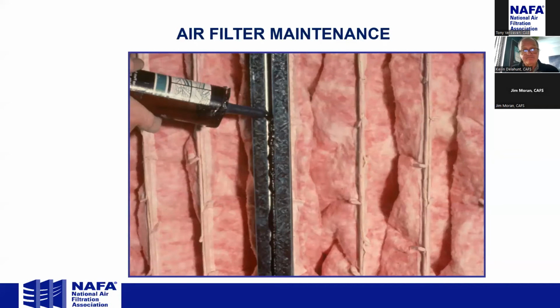Okay. Bag filters are a pretty common product in a lot of commercial buildings. In most cases, we like the air to hit it perpendicular, meaning that the air is actually helping in the seal by driving the filter into a gasket and a holding frame, as you saw in the picture back there. But in some cases, they're supplied as a side access in a U-channel tracking, and there could be 2 to 20 or 30 filters in a side access tracking.